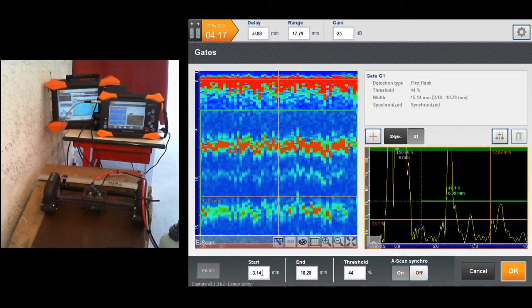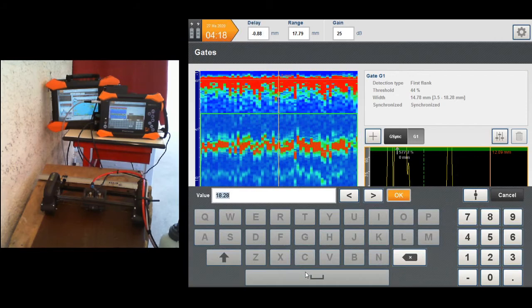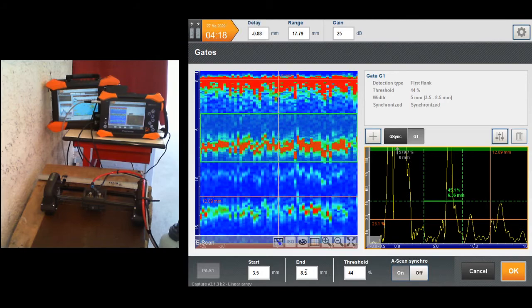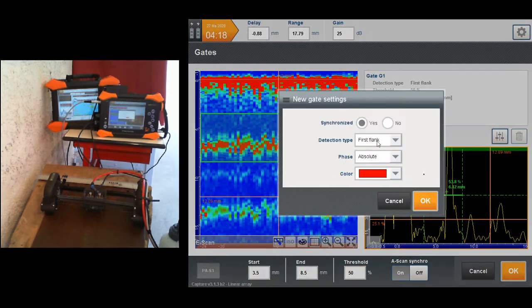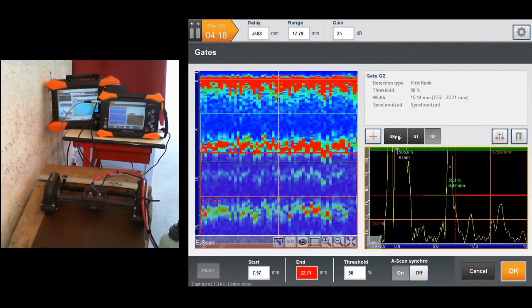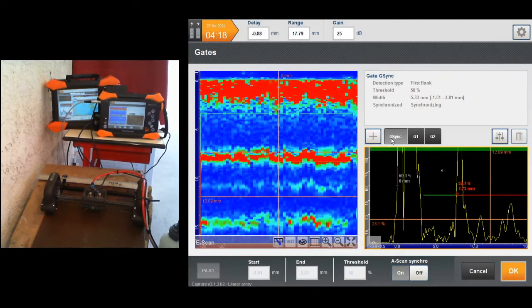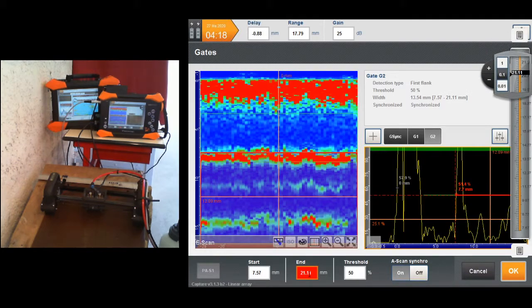So then if I move my gate, let's say to 3.5, because my procedures say I don't need to go closer than that, everything below 3.5 has to be detected, and that's fine. That's my gate. I can keep this one at 50 millimeter, 50% as well, and why not add one more gate on the first flank as well. So I must check that. Yes, my gate here is max peak. I must be consistent to have something accurate between the gates. Some procedures, or recommendations given by OIS, say that you need to use first flank. Good. G1 is first flank as well. G2 as well. Great.